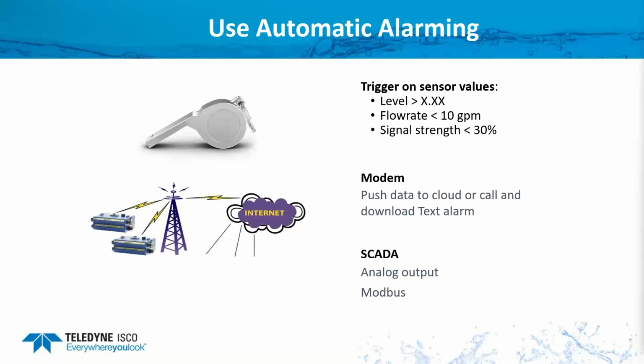So the different ways to be alarmed is that, if you're pushing the data to a cloud, you can have it send you a text message, send you an email. If you have data going out to your SCADA system via analog output or Modbus, you should be able to program your SCADA for similar alarms.